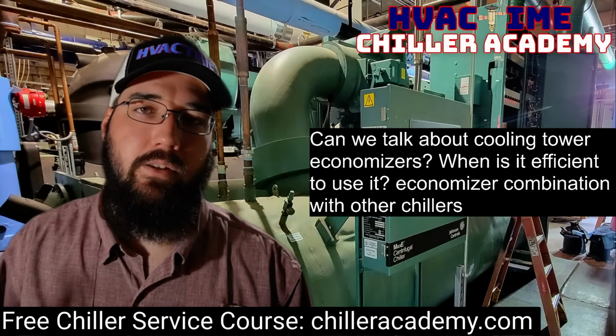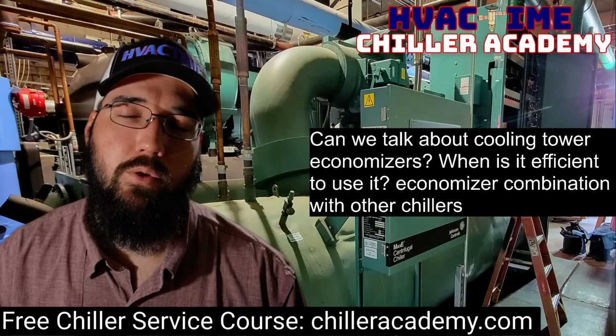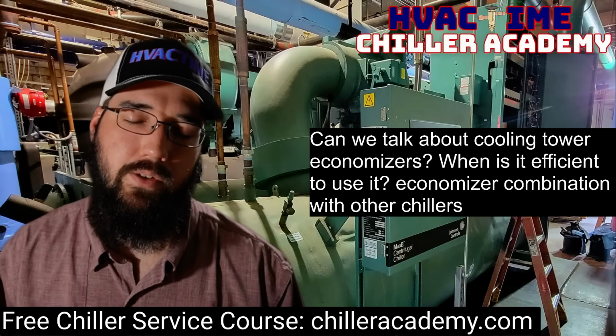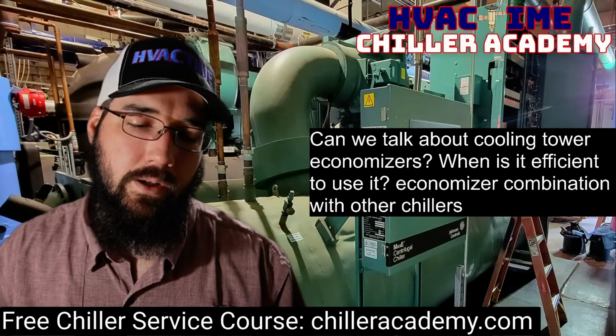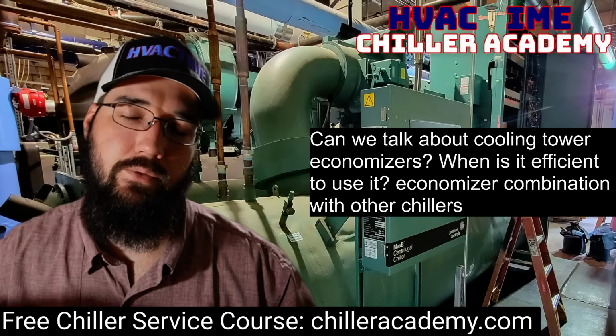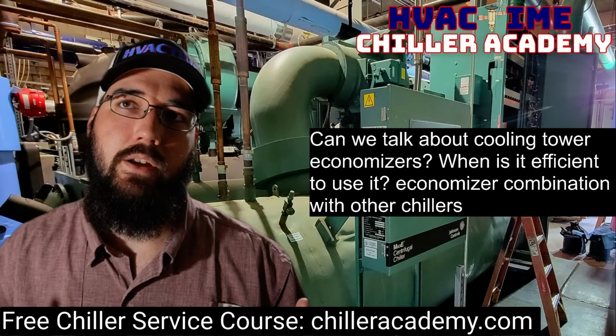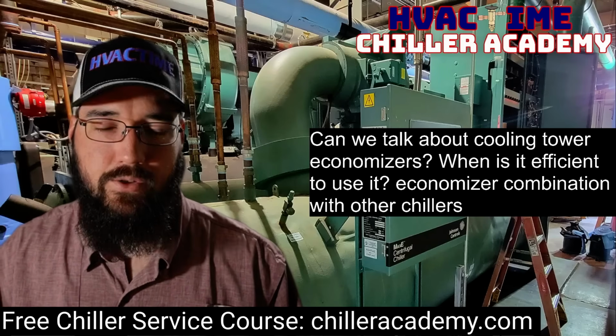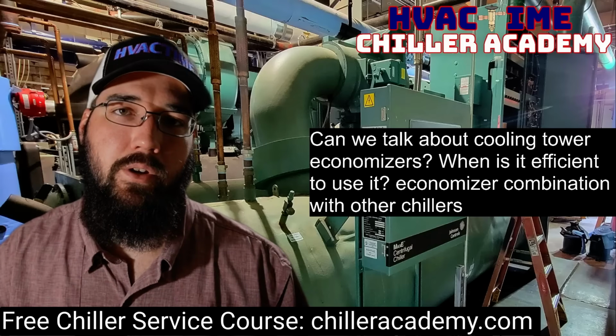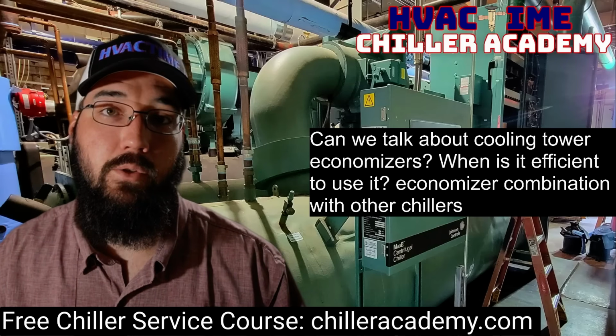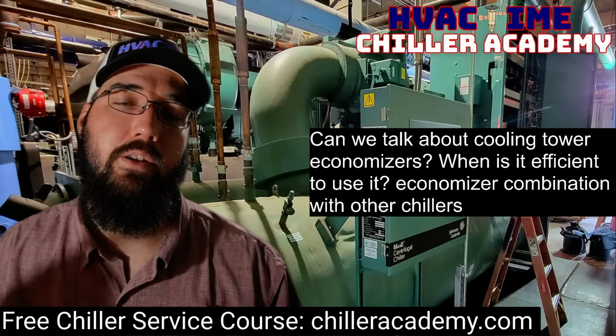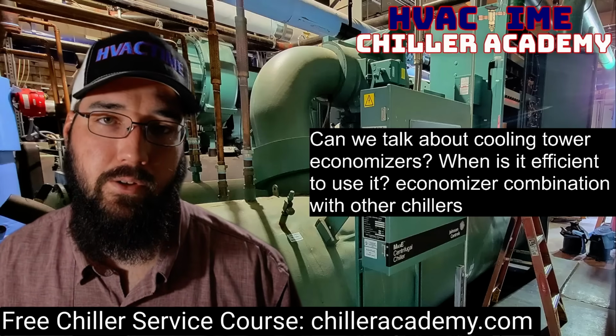Another one would be, and this was something Turbo Cores give me all kinds of fits on. With the Turbo Core, they need the pressure differential for cooling, because their standard package does not come with a liquid cooling pump to pump the liquid refrigerant from the condenser through the compressor.